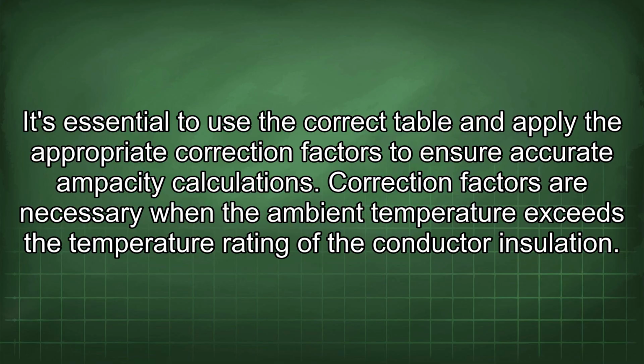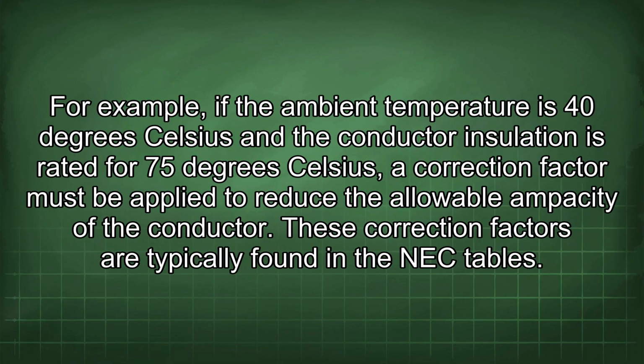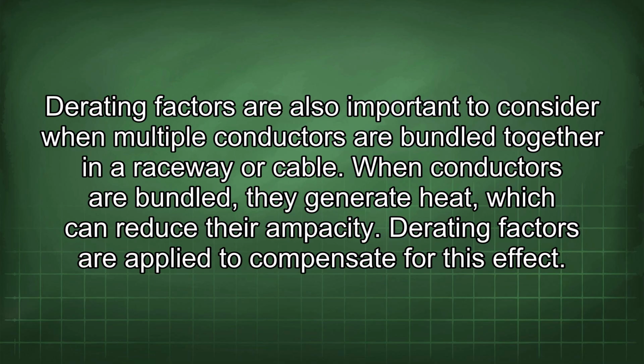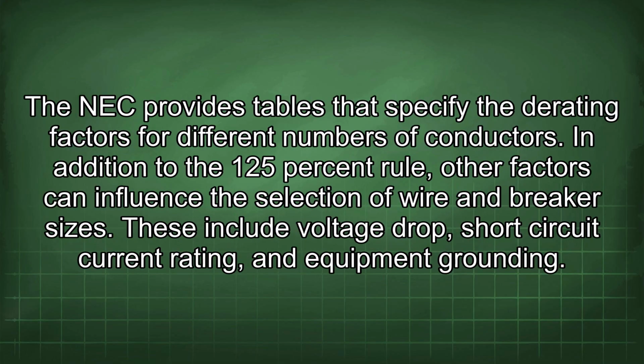Correction factors are necessary when the ambient temperature exceeds the temperature rating of the conductor insulation. For example, if the ambient temperature is 40 degrees Celsius and the conductor insulation is rated for 75 degrees Celsius, a correction factor must be applied to reduce the allowable ampacity of the conductor. These correction factors are typically found in the NEC tables. Derating factors are also important to consider when multiple conductors are bundled together in a raceway or cable. When conductors are bundled, they generate heat, which can reduce their ampacity. Derating factors are applied to compensate for this effect. The NEC provides tables that specify the derating factors for different numbers of conductors.